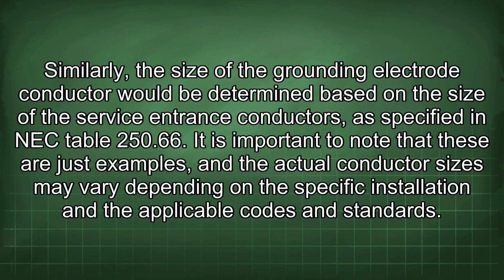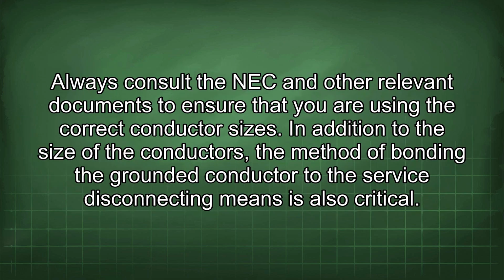Similarly, the size of the grounding electrode conductor would be determined based on the size of the service entrance conductors, as specified in NEC Table 250.66. It is important to note that these are just examples, and the actual conductor sizes may vary depending on the specific installation and the applicable codes and standards. Always consult the NEC and other relevant documents to ensure that you are using the correct conductor sizes.